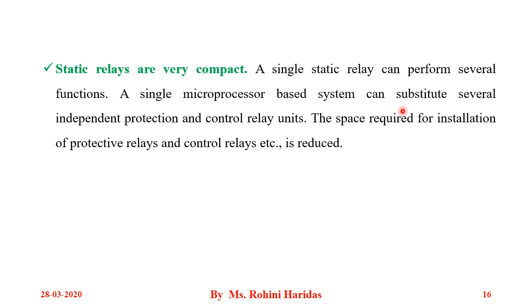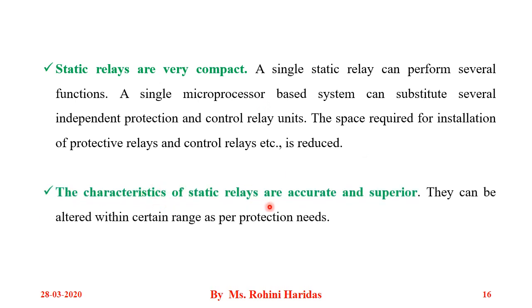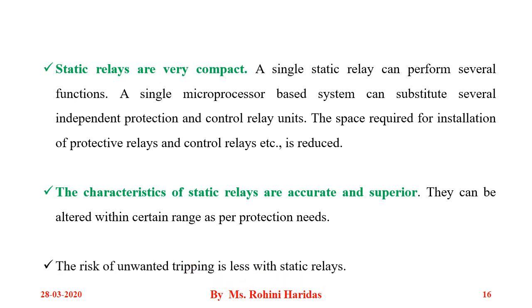A single microprocessor-based system can substitute several independent protection and control units. The space required for the installation of protective relays and control relays is reduced. For example, under-voltage protection, over-voltage protection, under-frequency protection, over-frequency protection, etc., can all be combined in a single unit, making static relays very compact. The characteristics of static relays are accurate and superior, and can be altered within a certain range as per protection needs. The risk of unwanted tripping is less with static relays.